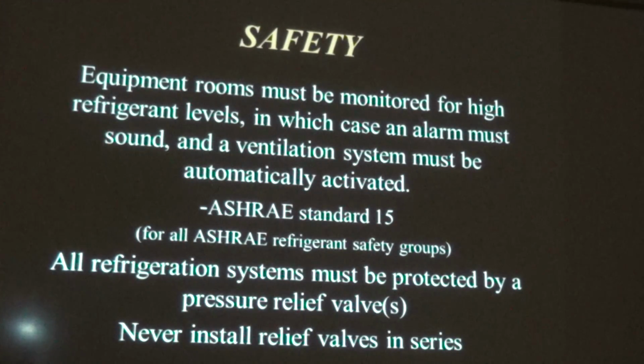In this case, we have another standard, ASHRAE Standard 15. Why, you may ask, is there another standard? The other one was for the refrigerant that displaced the oxygen because it's heavier. But remember, this refrigerant, R123, a B1, is toxic. So we have a double hit here, because it's toxic, you can't breathe it. So we have ASHRAE Standard 15. The room must be monitored for high refrigerant levels, in which case an alarm must sound and ventilation must be automatically activated.